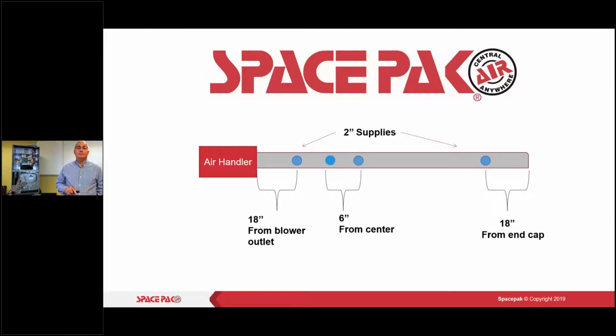So there's a drawing of it to show you what we're talking about. 18 inches from the blower, 6 inches on center between my drops, and 18 inches away from the end of the plenum is your last drop. Any questions on that, gentlemen?